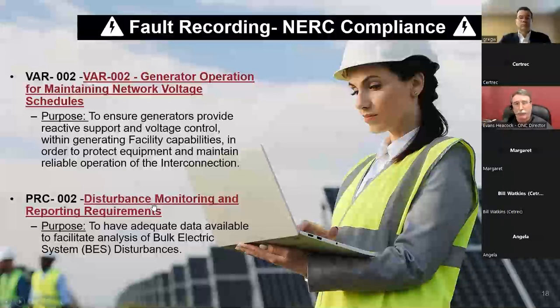It can also help from a standpoint with VAR2, which is generator operation and maintenance network voltage scheduling. If a site doesn't have good ways of monitoring this information, this also works pretty well to make sure they can say, yes, we have what we need. If you haven't had recording capability, this can also do recording to show they stay within their voltage requirements set out by the transmission provider. So this can help from a NERC standpoint also.